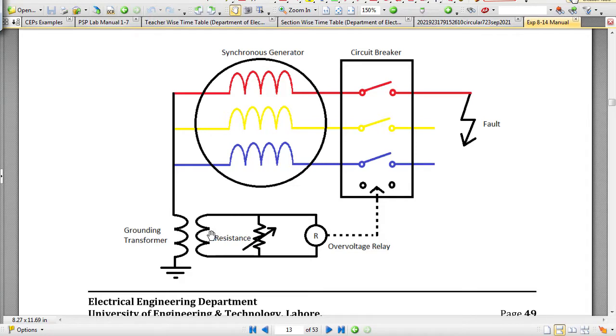step down transformer. Its primary voltage is rated either equal to or greater than the line to neutral voltage of the synchronous generator, and the secondary voltage is rated normally at either 120, 240 or 480 volt. So in this way that will become our distribution transformer, where the high voltage side will be in the range of distribution primary voltage and the low voltage side will be at distribution utilization voltage level.